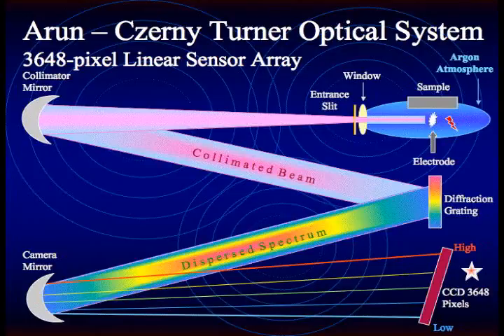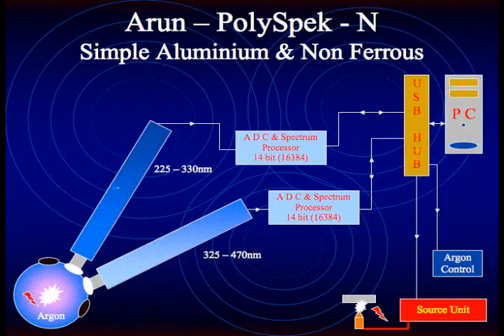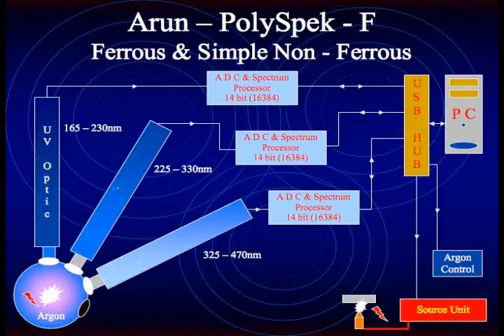Several versions of the PolySpek are available depending on your application. The most basic model is the PolySpek N, which utilizes two optical cells for analysis of common non-ferrous metals. The PolySpek F includes a third argon purge optic, which will allow measurement of most ferrous metals, including the analysis of carbon, phosphorus, and sulfur.